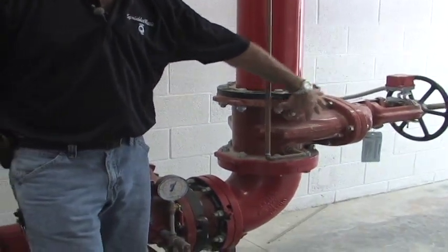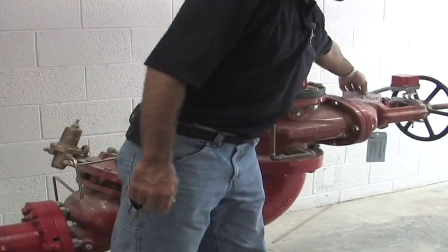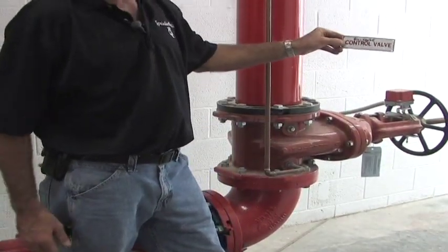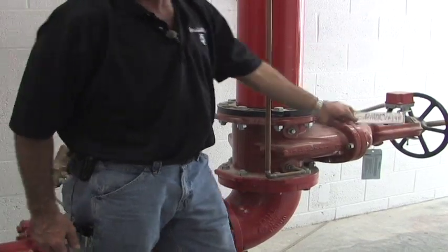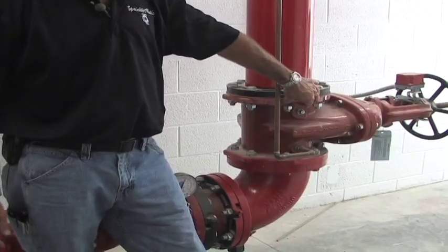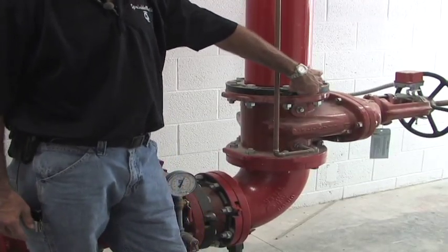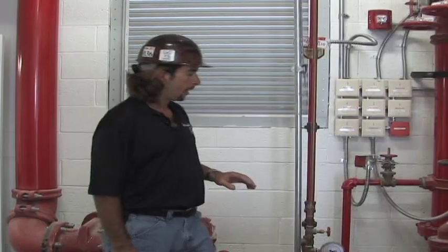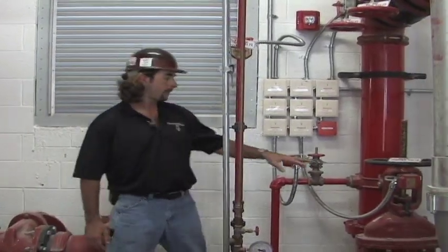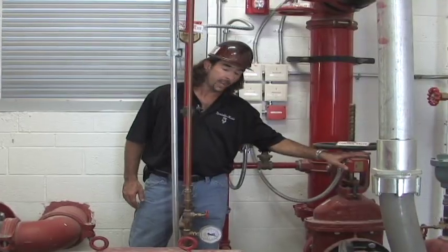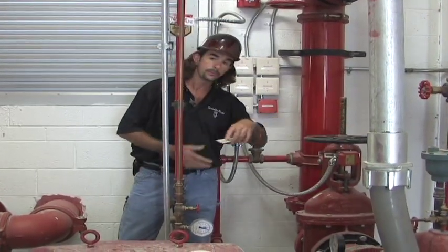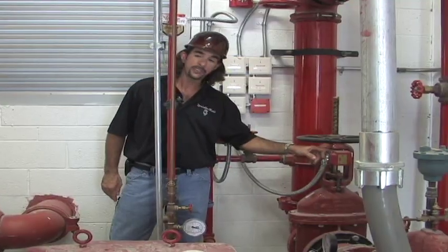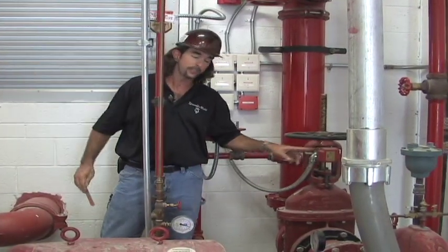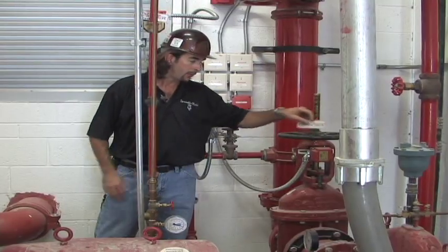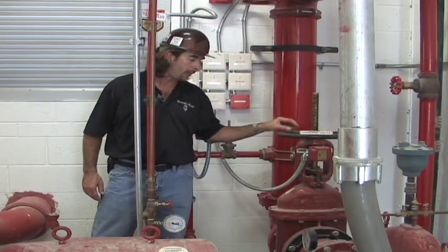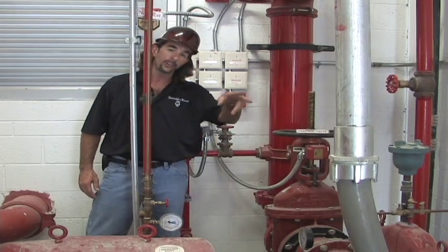Over here to my far left, we have an OS&Y valve, which is going to be our discharge control valve. By shutting this valve off, we kill all water supply to the building from the fire pump. All of our control valves have a tamper switch on them. Each time one of these valves is shut with a turn of 5 turns, you would get a tamper, which is going to go back to your fire alarm panel saying that the valve is closed. Every time we do a weekly startup, we're going to make sure that all the valves are in the open position, except for our test header valve.